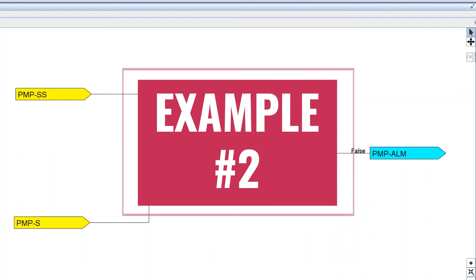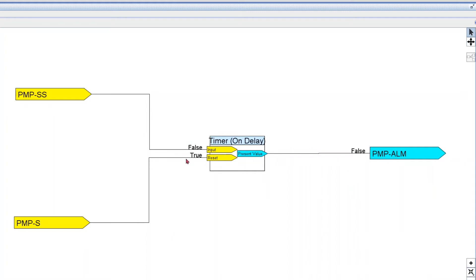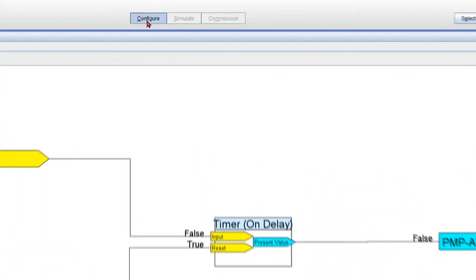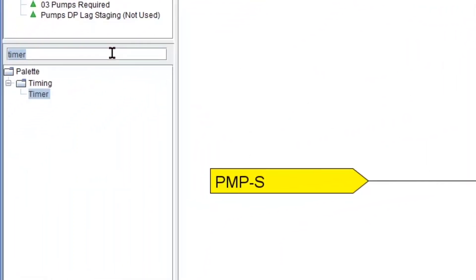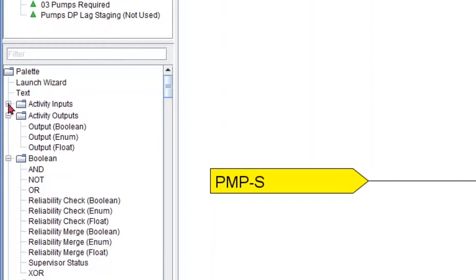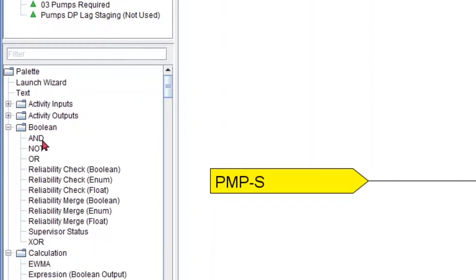Okay, example number two. We want to generate an alarm when we have a start command and no status — which the timer can handle — but also when we have no start-stop and we do have a status. Basically, any time there is a mismatch between my start-stop and my status. The key to accomplishing this will be using an XOR. So I'm gonna exit simulation and look for my boolean folder with the basic logical gates — AND, NOT, and OR — but now we're gonna use an XOR, and I'll explain why.